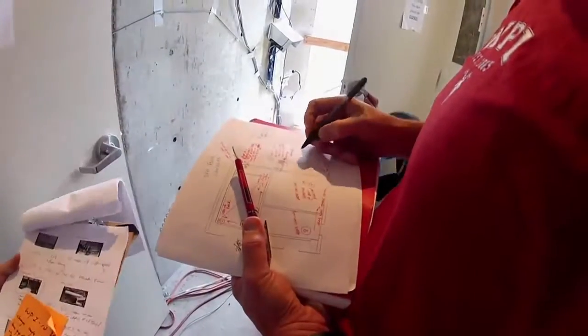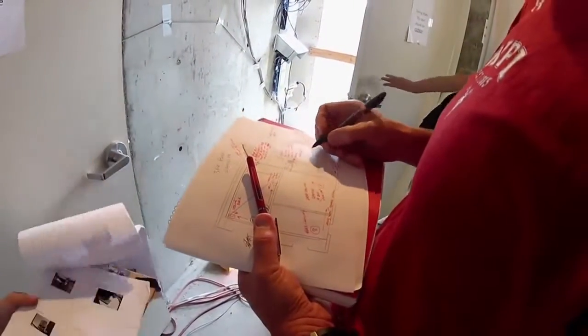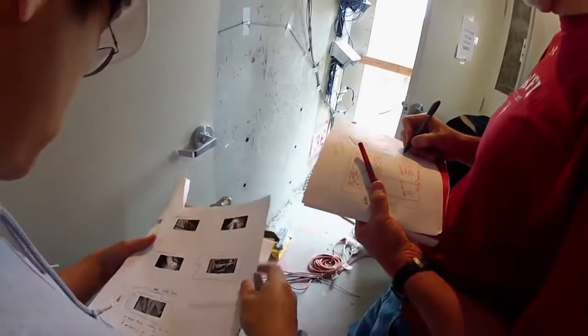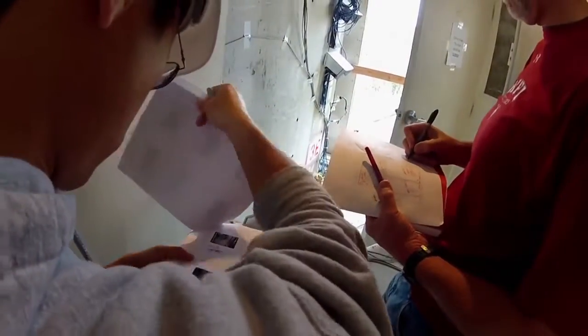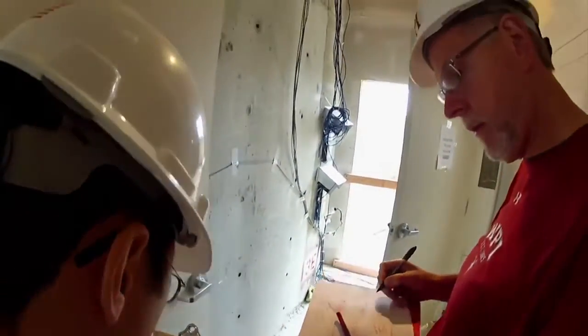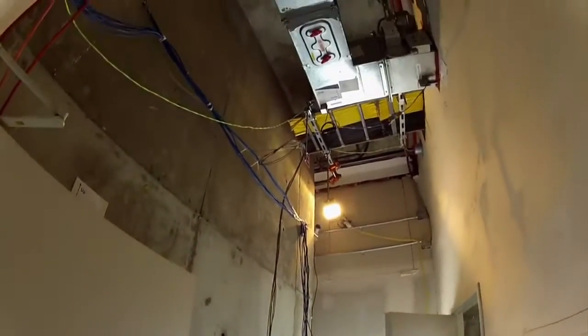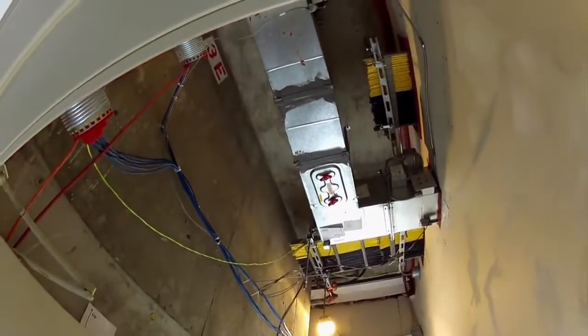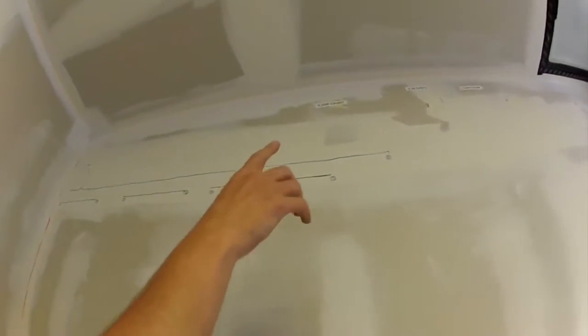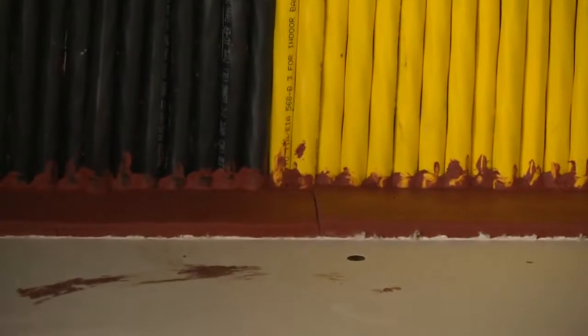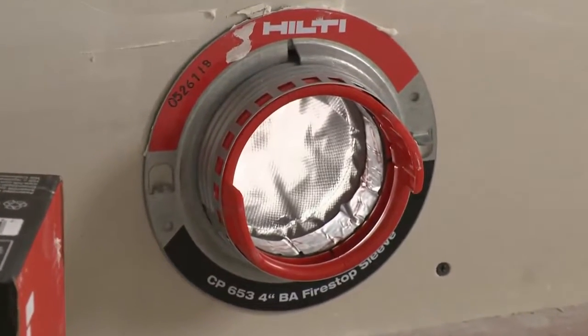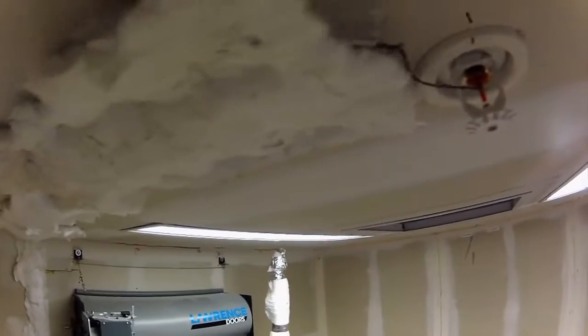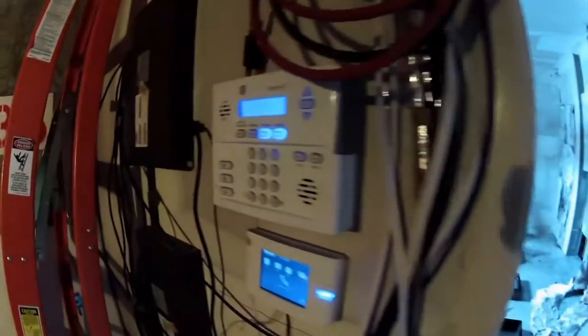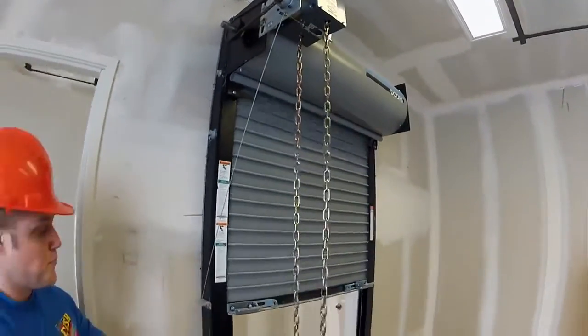With seismic testing complete, it is time for fire testing. Led by Brian Meacham from Worcester Polytechnic Institute, these tests will for the first time anywhere observe how fire protection measures perform after seismic events. These measures include passive elements, as simple as wall joints or specially designed fire blocking and stop materials that activate under heat, as well as active systems like sprinklers, alarms, and a heat-activated fire door.